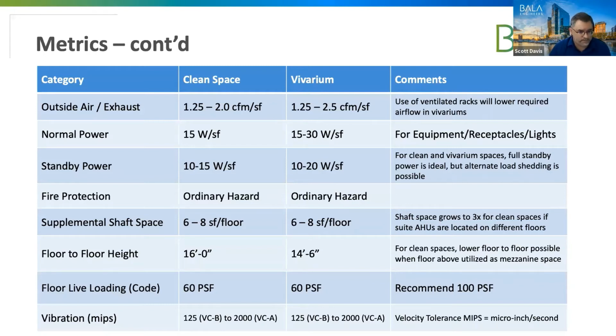Looking at vivarium, they are similar to your typical lab from what we're seeing. Again, a range of about 1 to 2.5, a little higher than your typical lab, and the range is going to be predicated upon the type of animals housed. So if you're looking at, say, swine or canine, you're going to be on the larger end, the 2.5 CFM per square foot. If you're dealing with rodents in racks and individual cages, you could be on the lower end.